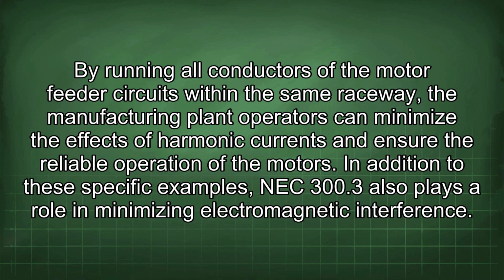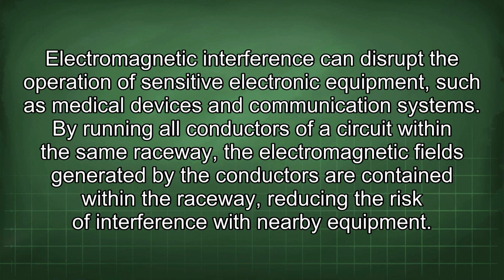By running all conductors of the motor feeder circuits within the same raceway, the manufacturing plant operators can minimize the effects of harmonic currents and ensure the reliable operation of the motors. In addition to these specific examples, NEC 300.3 also plays a role in minimizing electromagnetic interference. Electromagnetic interference can disrupt the operation of sensitive electronic equipment, such as medical devices and communication systems.